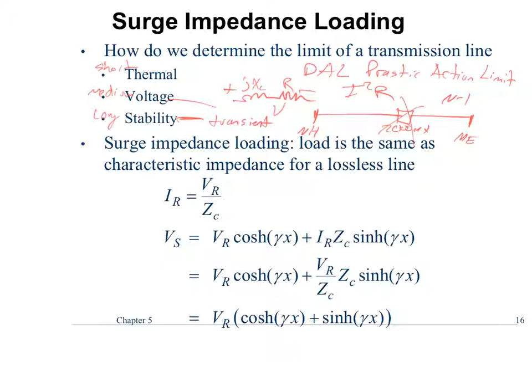But it's getting a little interesting, and that's why there's a static VAR compensator. I know a number of people in this class have been to Chester to see it. That was installed to help improve stability, and it's only about a 90-mile line into Canada. It increased the line capacity by 200 megawatts, even though it's only a 40 megavar SVC.